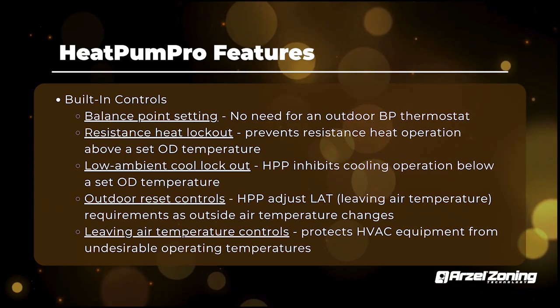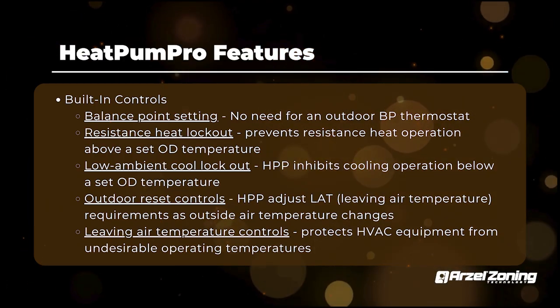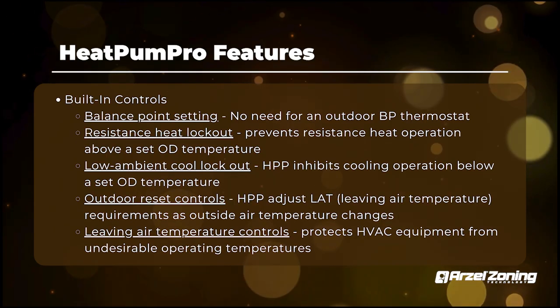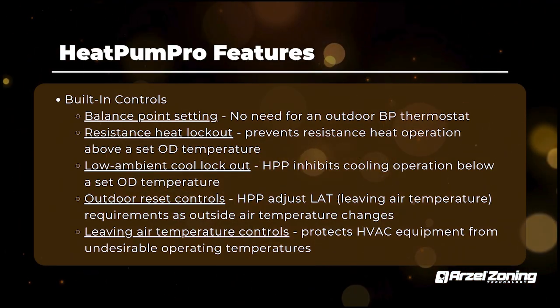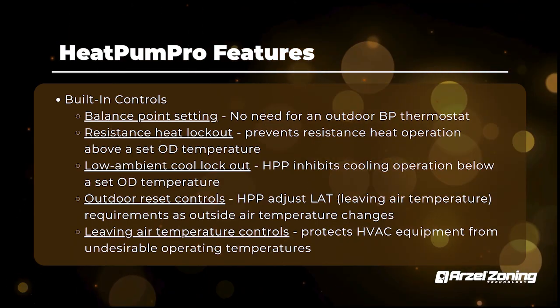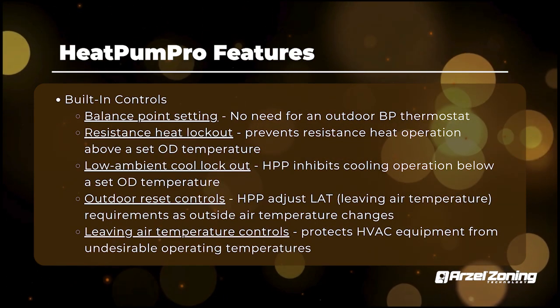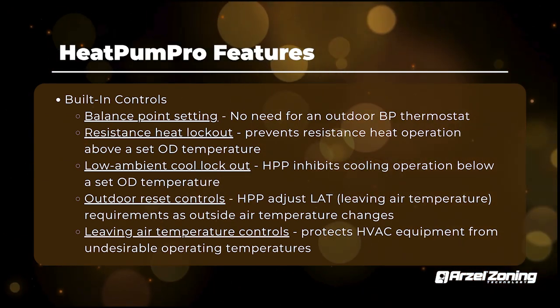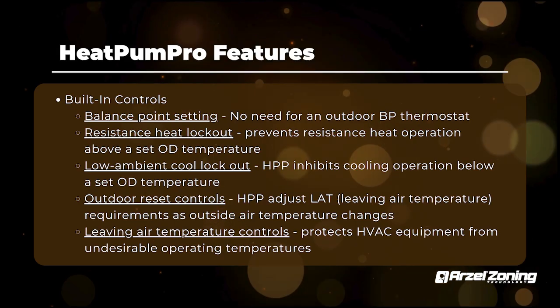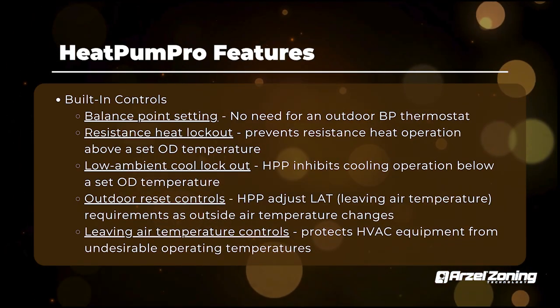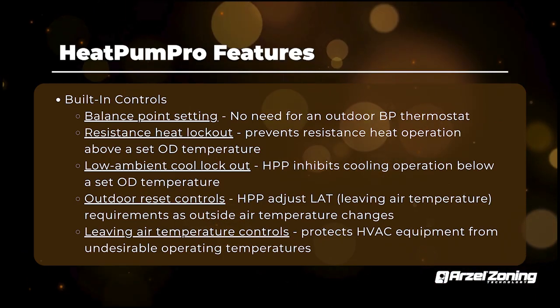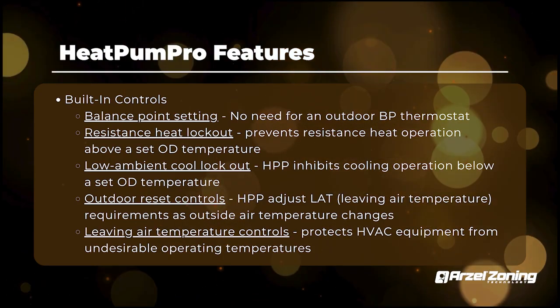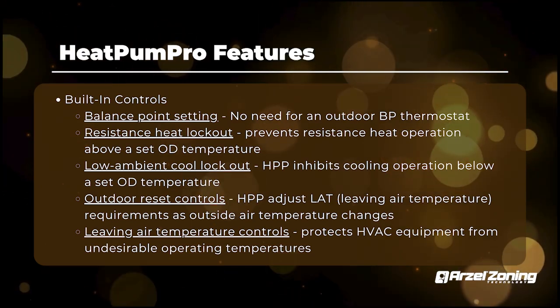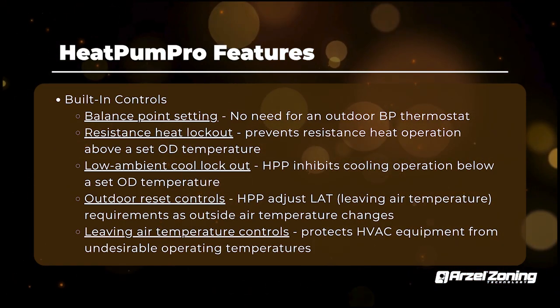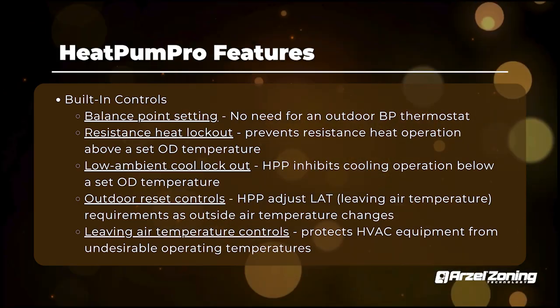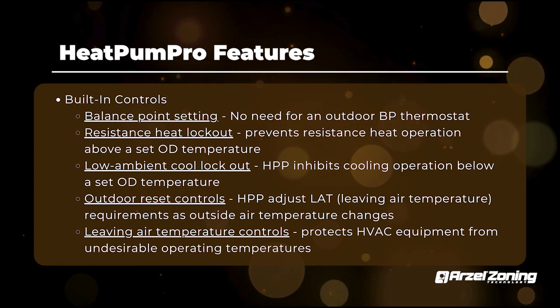It also has your resistance heat lockouts, so it'll give you hard lockouts on your electric heat source, and that'll just give your guys more energy efficiency for your customers so they don't have to run that auxiliary heat when you don't actually need it. That's based on outdoor air temperature and runtime. And this is kind of field adjustable, so you can change this to temperatures, and then you can also set it to a lock-in feature. And essentially, if it's set to lock in, it would engage those heat strips anytime it is needed. And that's based off of runtime. So if it can't maintain temperature after 6 minutes, it would kick on your auxiliary heat if it's set to the lock-in function. So essentially, anytime it would be needed, it would engage them, and there's no hard lockout in that feature. So it's up to you if you guys want to do a hard lockout or just leave it as is and let it engage as needed.